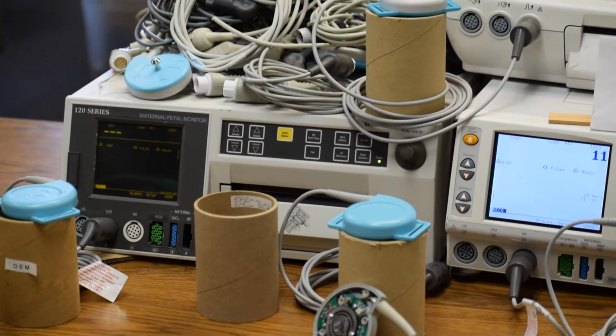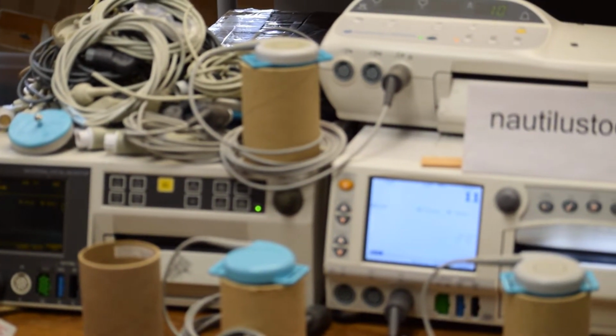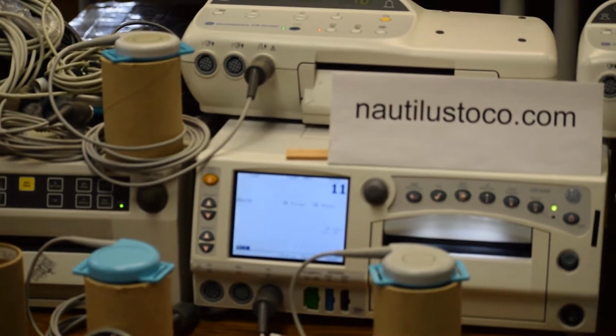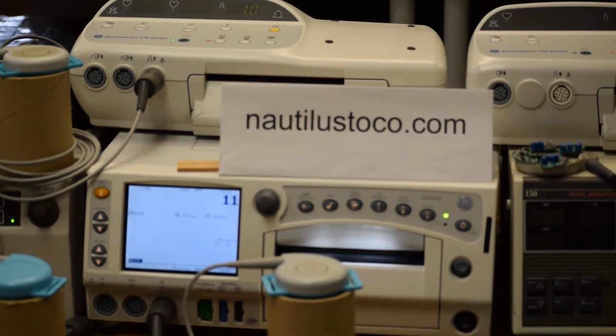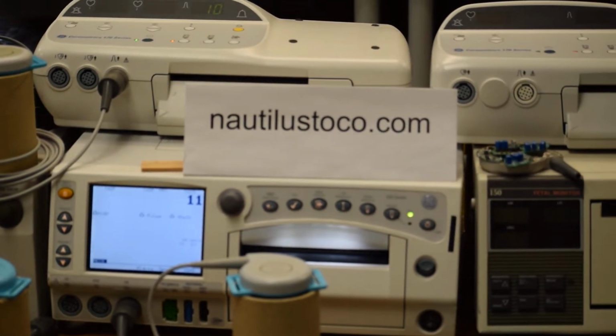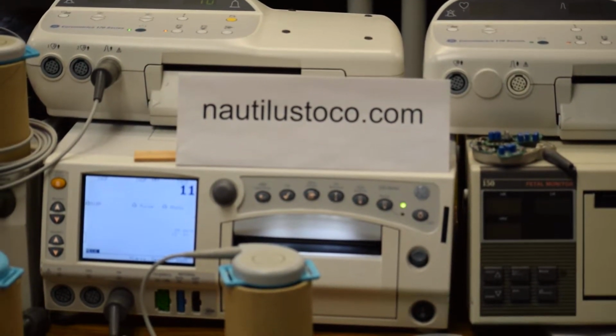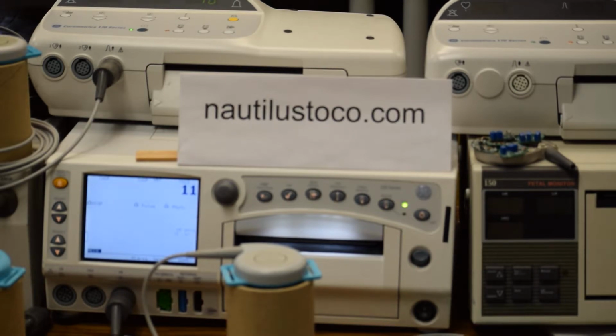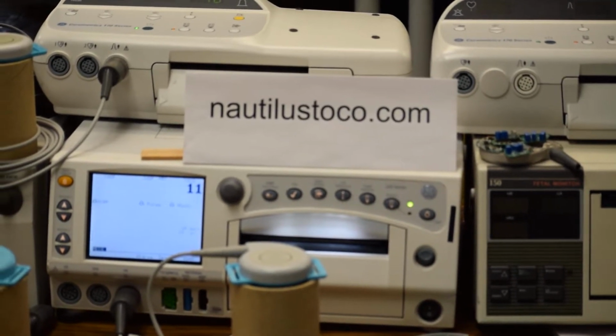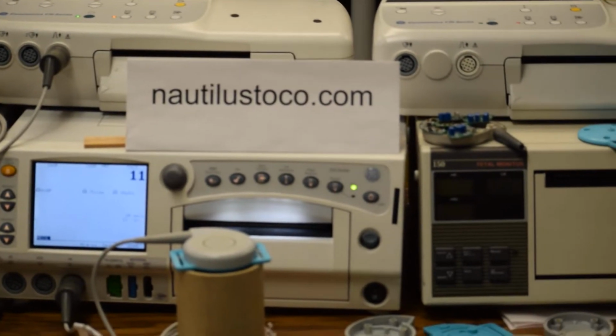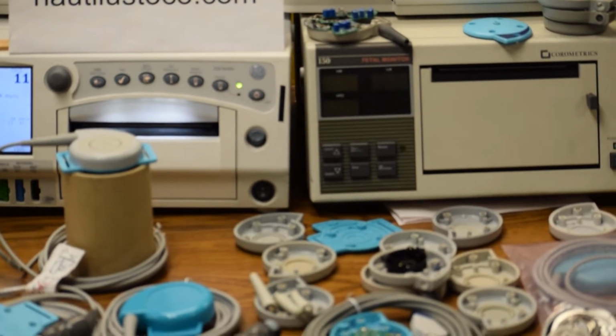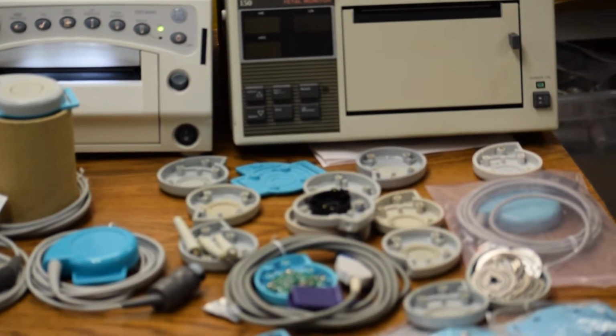Out of the other 3 transducers, the one with the off-white molded non-OEM connector, and the other 2 which look like the original gray connector, there is no way they can be brought back to GE specifications as the PCB is not from GE. The plastic resin material used is of far inferior quality, with slightly larger diameter pins with non-conformal plating that results in galvanic voltage buildup. The leakage current between the pins keeps varying, ultimately resulting in extremely poor stability of baseline as complained by the biomedical engineering manager. At times, the random noise gets amplified and causes erratic Toco waveform tracing.